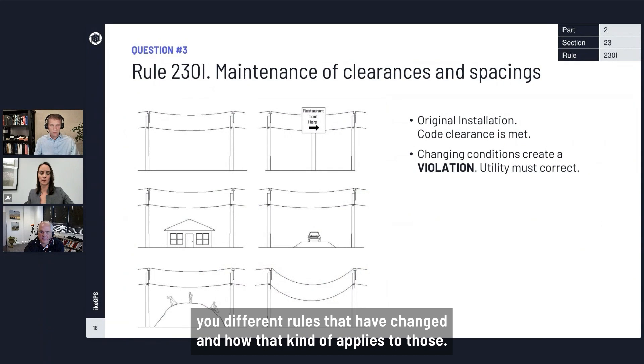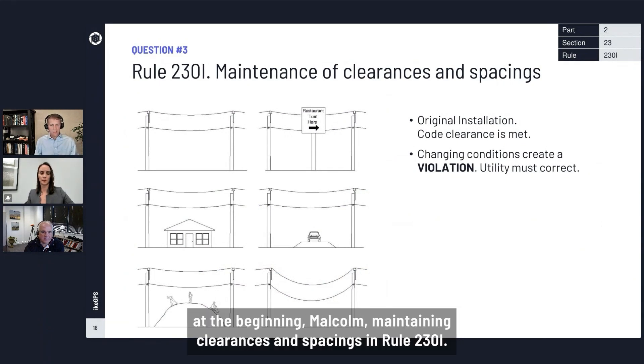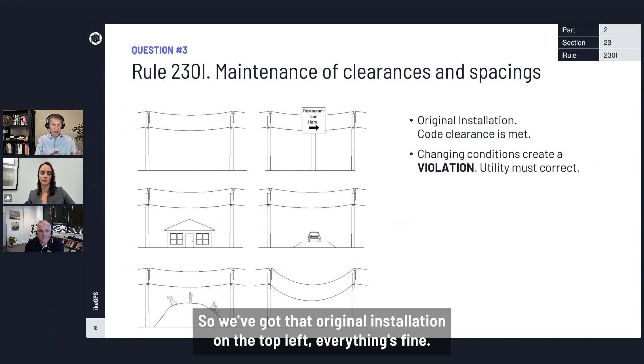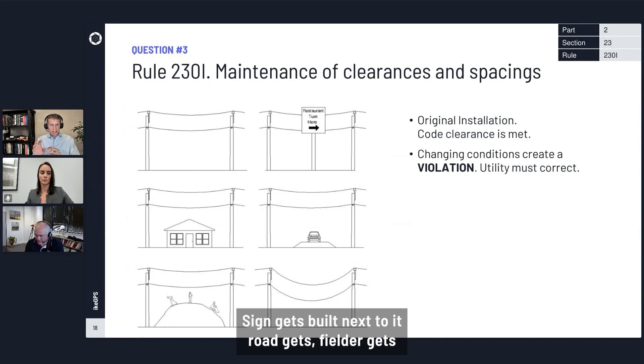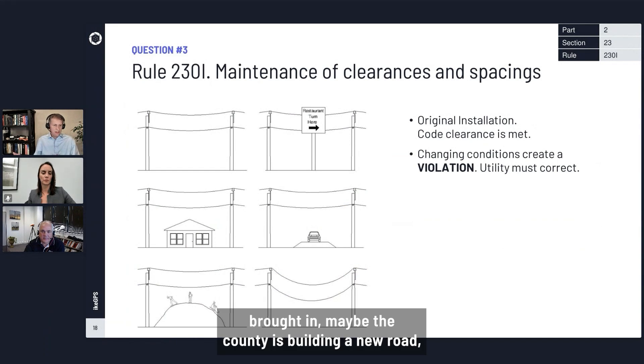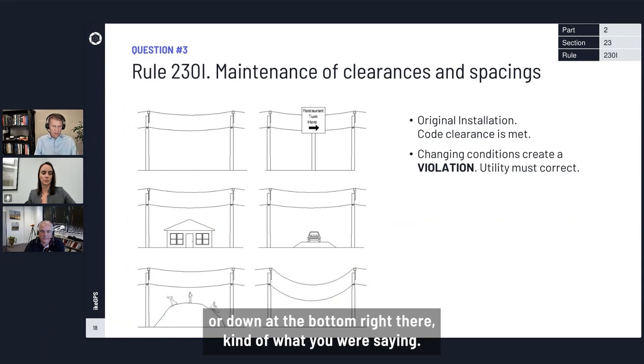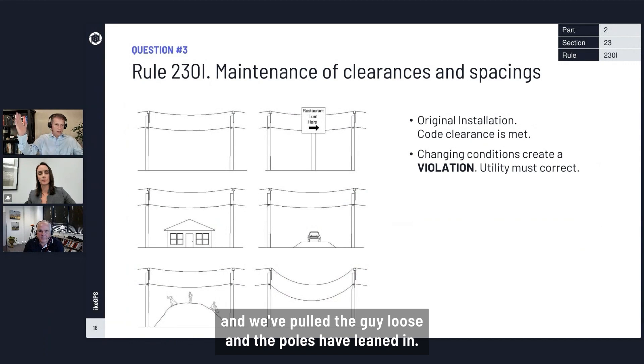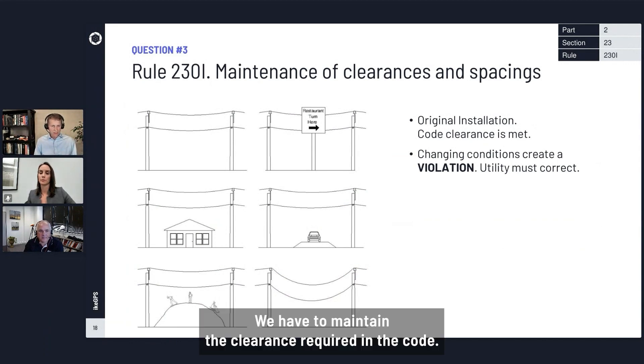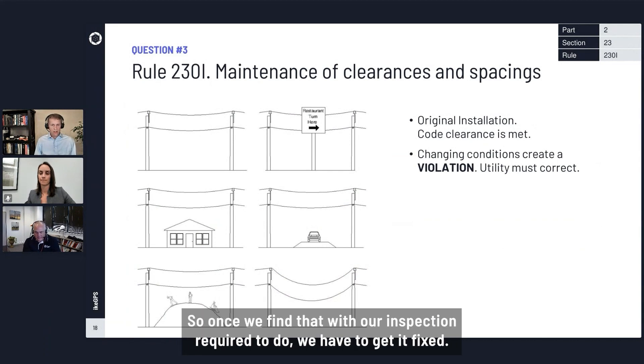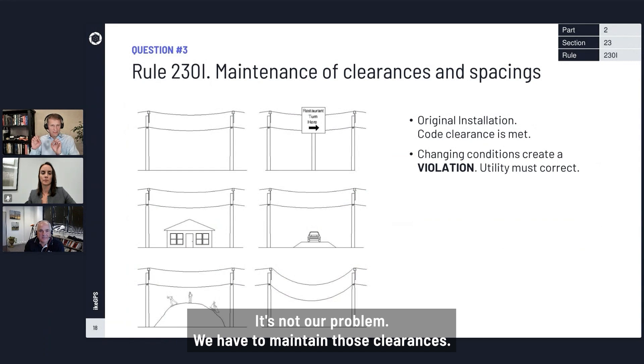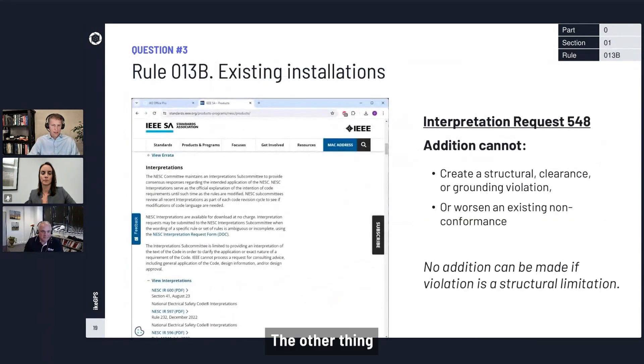Rule 230i deals with maintaining clearances and spacings — this is sometimes where people misapply the idea of the grandfather clause. We've got an original installation on the top left where everything's fine, and then changes happen: a sign gets built next to it, a road gets put in, or the structure gets deflected — maybe a big storm pulled a guy loose and the poles have leaned in. We have to maintain the clearances required in the code. We don't get to say 'well, that was there first' just because someone built a house under the line — we have to maintain those clearances.